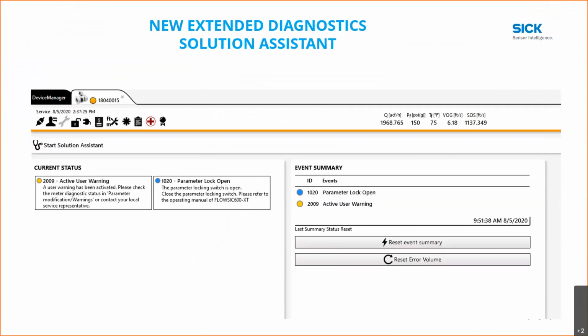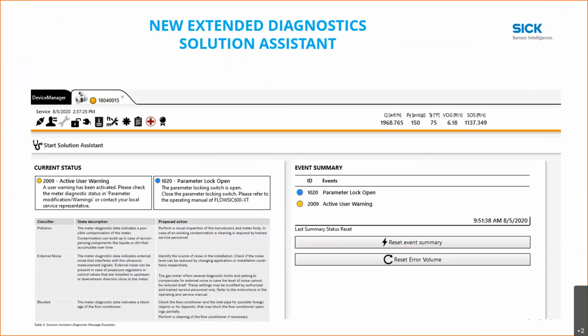If we go back to here, again, you start the solution assistant. And here are some examples of the proposed actions that may come up. Depending on what alarm is set, you may have a blocked flow conditioner or dirty transducers, or in this case, a failed electronics or transducer. Or in this case, it'll tell me, hey, Joel, plug the cable back in. So this is how the solution assistant can help the tech out in the field. And again, this is something new, new diagnostics that's available.